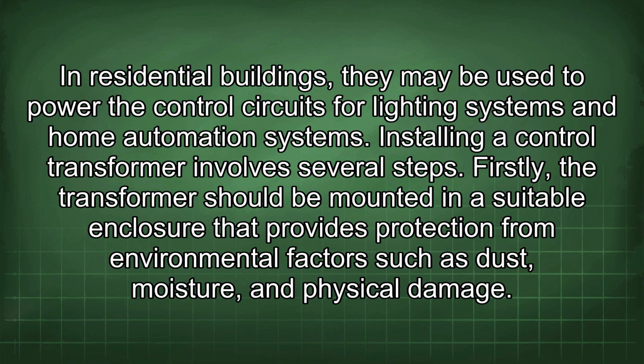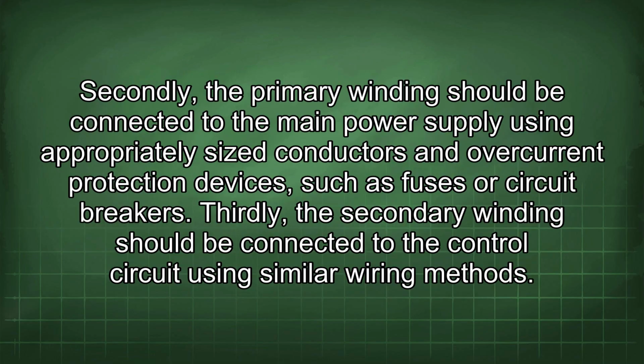Installing a control transformer involves several steps. Firstly, the transformer should be mounted in a suitable enclosure that provides protection from environmental factors such as dust, moisture, and physical damage. Secondly, the primary winding should be connected to the main power supply using appropriately sized conductors and overcurrent protection devices such as fuses or circuit breakers. Thirdly, the secondary winding should be connected to the control circuit using similar wiring methods.